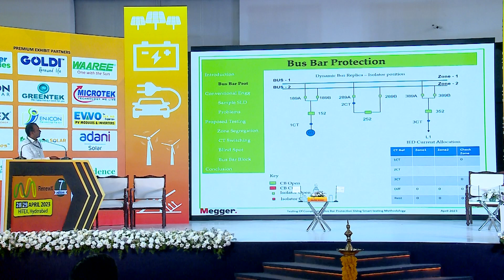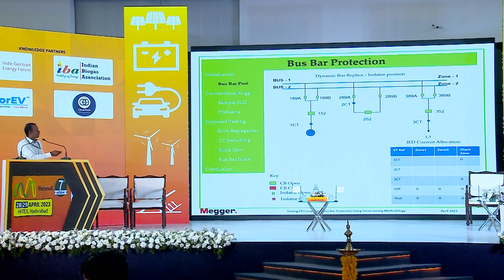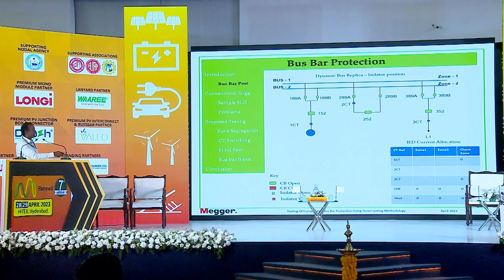And this is how the relay reads the current. The protection system will normally follow this table, and this table is based on the isolator positions. So for example, if the 89A isolator is closed, the respective zone will read the current, and that's what I'm going to show you in the next slide. So imagine the system is actually feeding through this. The solar feeds the bus 1, and from bus 1 the supply goes directly out. And during this, since 89A, that is the isolator connected to bus 1, is closed, we can see the current being read in zone 1.